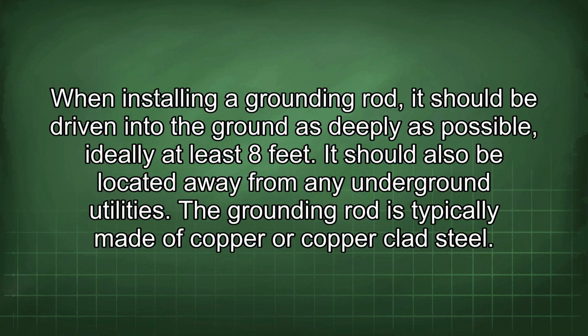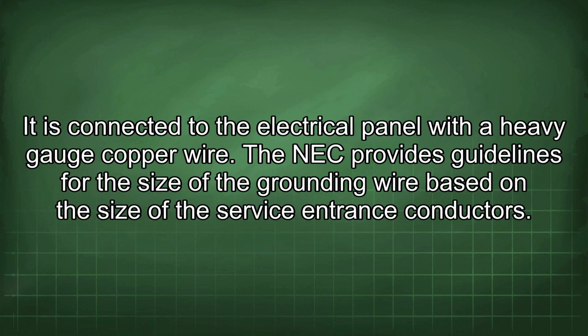When installing a grounding rod, it should be driven into the ground as deeply as possible, ideally at least 8 feet. It should also be located away from any underground utilities. The grounding rod is typically made of copper or copper-clad steel. It is connected to the electrical panel with a heavy-gauge copper wire. The NEC provides guidelines for the size of the grounding wire based on the size of the service entrance conductors.